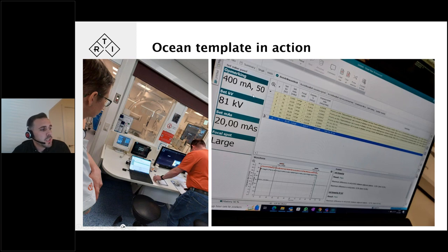In this display, on the left-hand side of the screen there are big values — this is the set value panel. To make it really easy for engineers to perform these tests, all the important information you need to see to make an exposure is shown large on the left. For example, in this exposure we want 400 mA, 81 kV, 20 mAs, and we want the focal spot in the large setting rather than small. You just make the exposure, make sure these criteria are fulfilled, and everything else is done automatically.